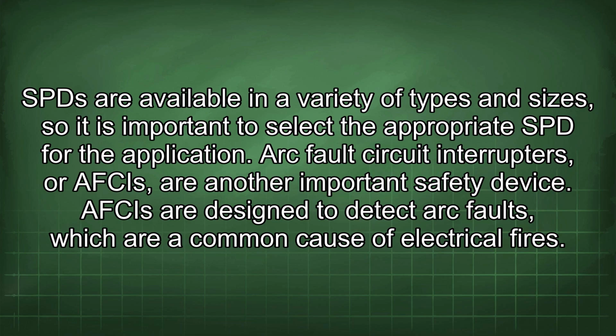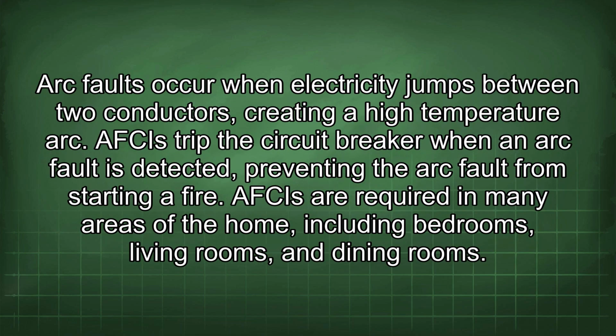SPDs are available in a variety of types and sizes, so it is important to select the appropriate SPD for the application. Arc fault circuit interrupters, or AFCIs, are another important safety device. AFCIs are designed to detect arc faults, which are a common cause of electrical fires. Arc faults occur when electricity jumps between two conductors, creating a high-temperature arc. An AFCI trips the circuit breaker when an arc fault is detected, preventing the arc fault from starting a fire. AFCIs are required in many areas of the home, including bedrooms, living rooms, and dining rooms.